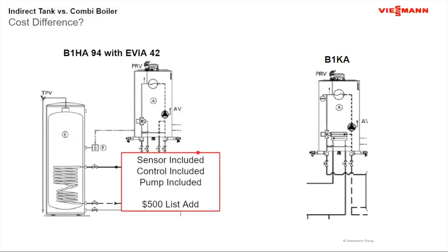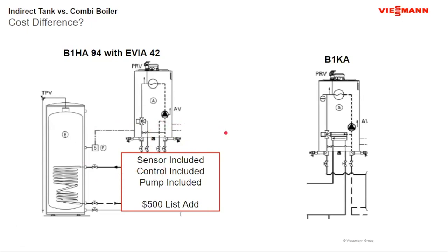In the package, the sensors are included, the controls are included, and the integral pump works both for the boiler loop pump and also the domestic pump. List price-wise, that's about a $500 add-on. So when you start to look at upselling features and selling the indirect with the combi, for somebody who's a good or average salesman, a $500 list adder over a piece of equipment they're expecting to last at least 20 years is a lot of times an easy sale to make.